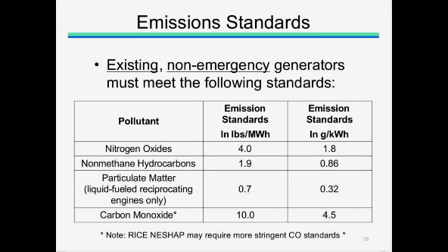This slide shows the emission standards which would apply to existing non-emergency generators under the model rule. The standards are shown in both pounds per megawatt hour and equivalent gram per kilowatt hour units for comparison purposes, since most emission standards set by the EPA for engines are displayed as grams per kilowatt hours. One thing to note with these standards is that they equate to an approximate 90% reduction in emissions from an uncontrolled diesel generator. The state of Delaware is utilizing these standards, and they are currently being met by existing non-emergency generators operating in the state.